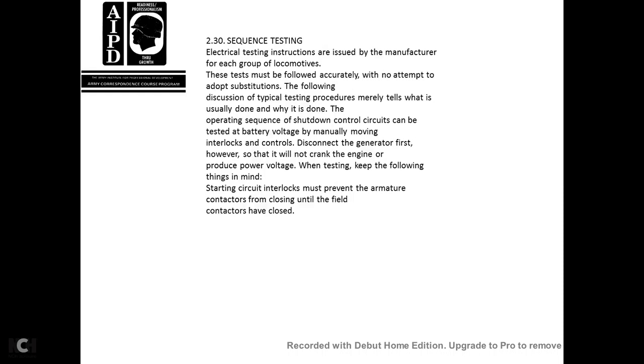2.30. Sequence testing. Electrical testing instructions are issued by the manufacturer for each group of locomotives. These tests must be followed accurately with no attempt to adopt other solutions. For the following discussion, the typical testing procedure will merely state what is usually done and why it is done. The operating sequence of shutdown control circuits can be tested with battery voltage by manually moving the interlocks and controls, disconnecting the generator first so that it will not crank the engine and produce power voltage. Then test, keeping the following things in mind.